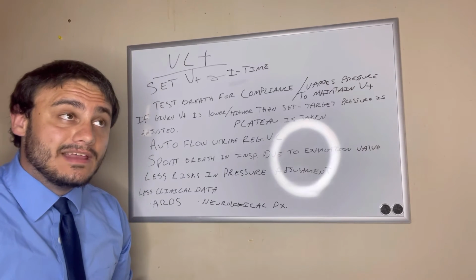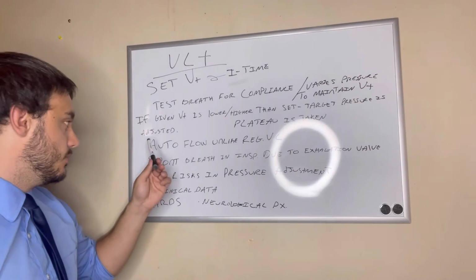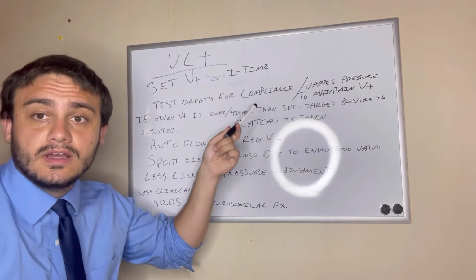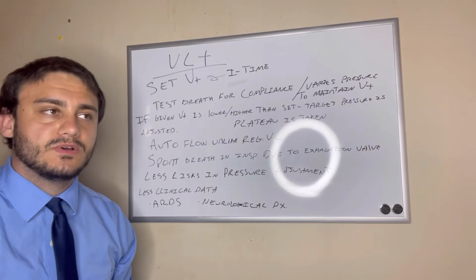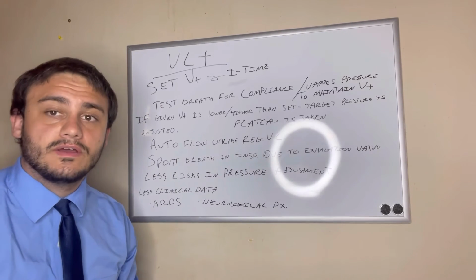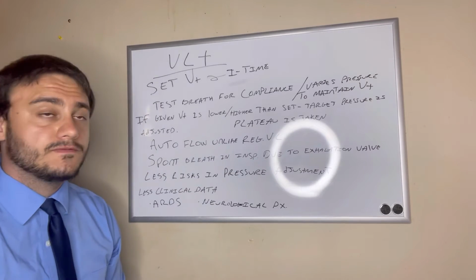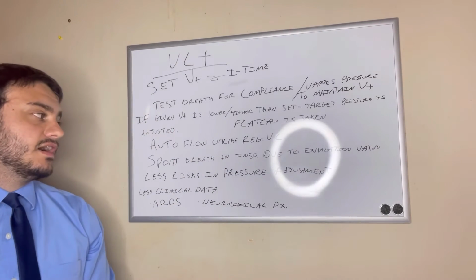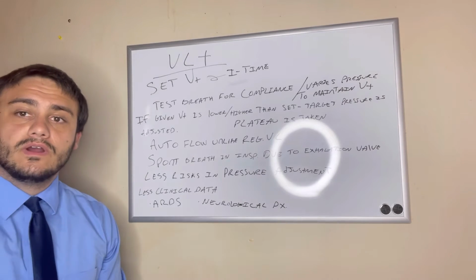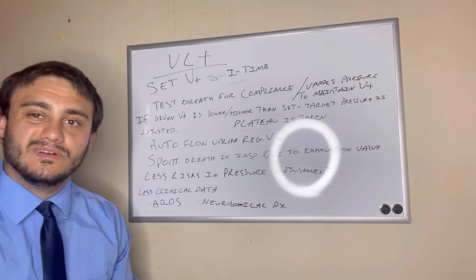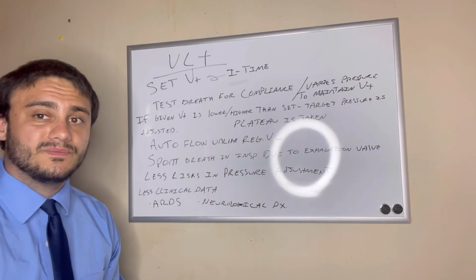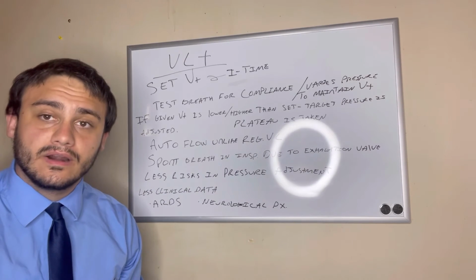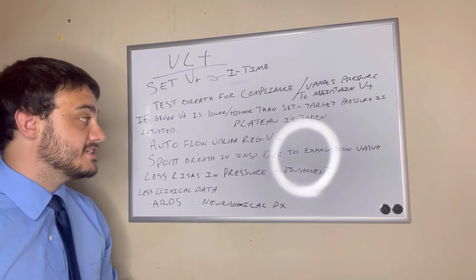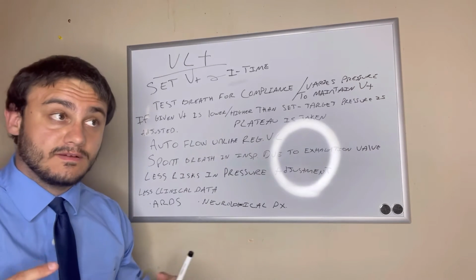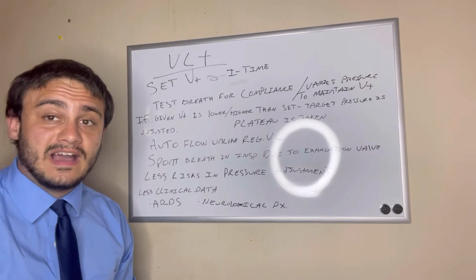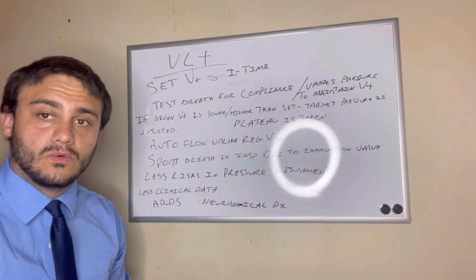And this is more of a patient comfort thing, whereas with autoflow or volume control plus, the flow is adjusted breath to breath. So if a patient wants to take a faster breath, they can go at their own pace. And this is a patient comfort feature of volume control plus that you'll see used with neurological patients, where they have trouble synchronizing with the vent and they kind of want to do their own thing. Whereas if you set a flow, you could get some asynchrony in there. So volume control plus can be useful in that aspect because the patient wants to do their own thing. Maybe they're just not consistent with how fast they want to take their breath. So they want a faster one or a slower one.